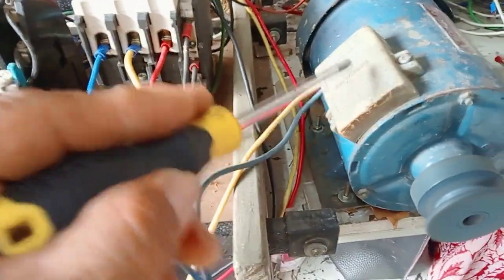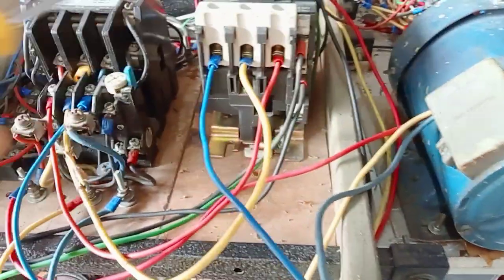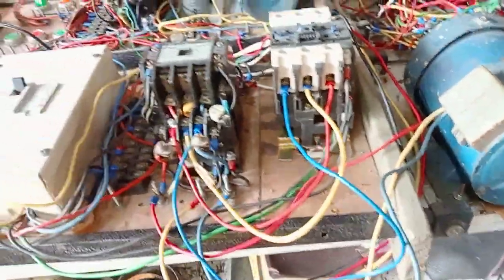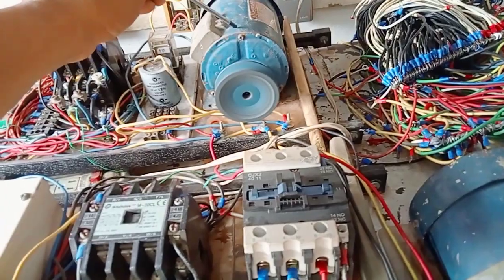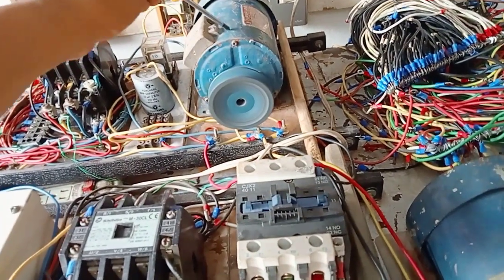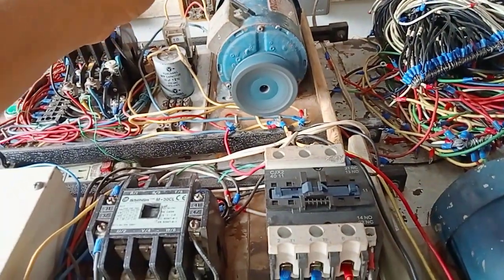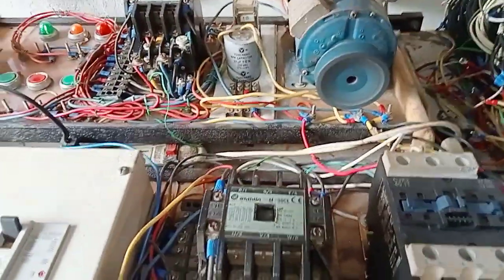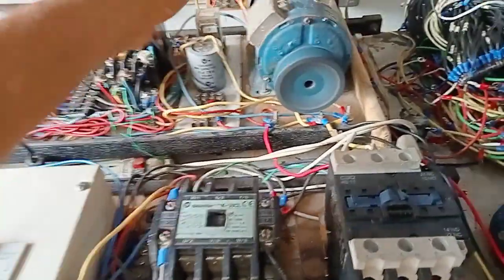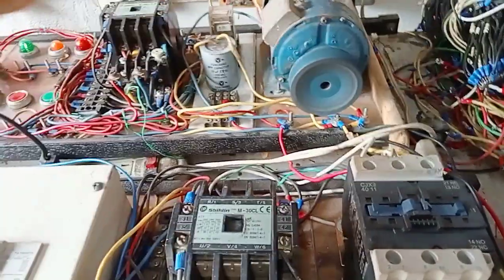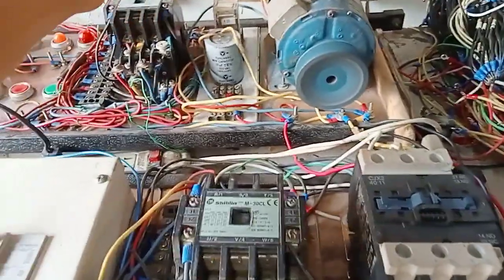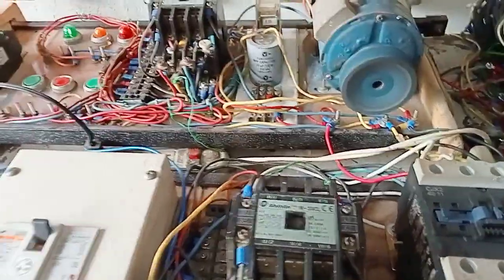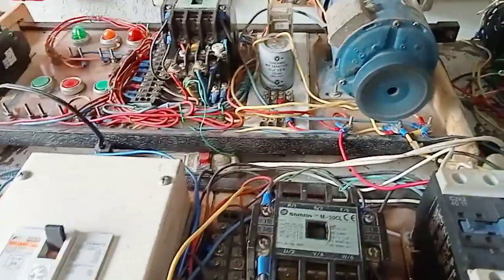Aside from running normally, we can also reverse and run forward. So take note: if a 3-phase motor runs in single phase without this control, within a split second the motor will burn out. But with this setup, even if you run it for hours or days, the motor operates normally.